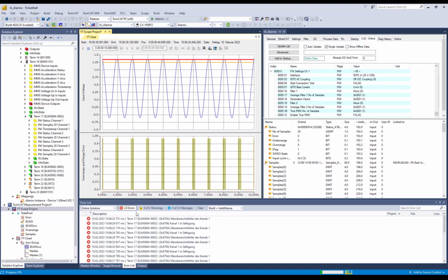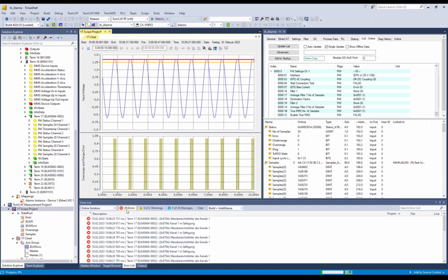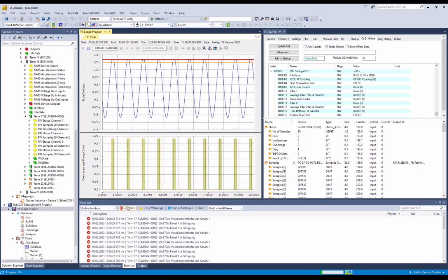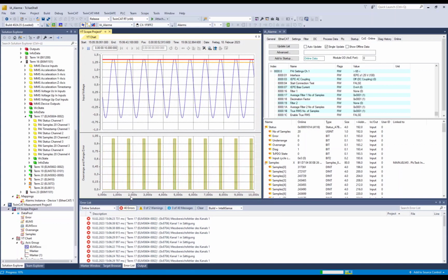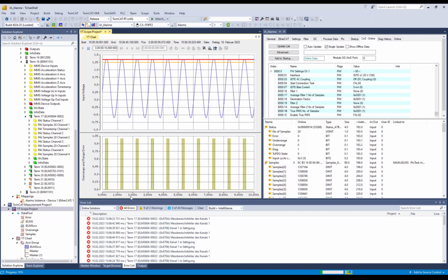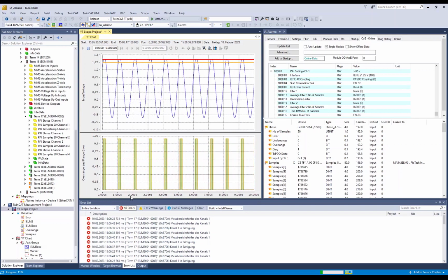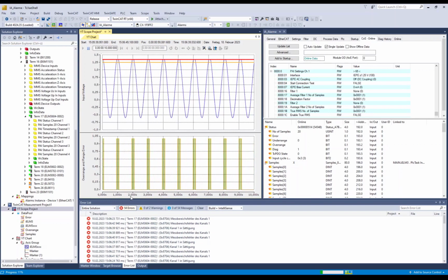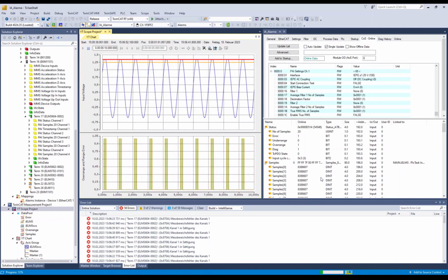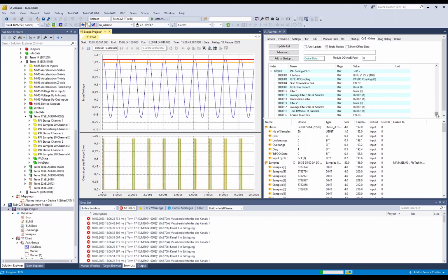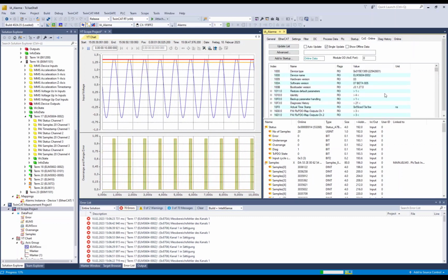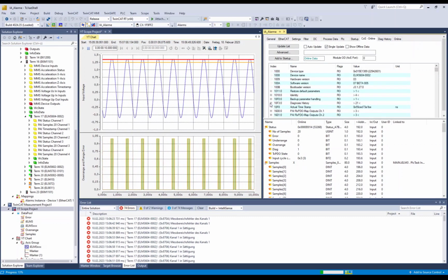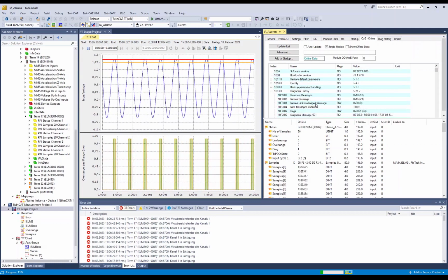And I want to get rid of these errors. You see that it's counting. So if you have lots of exceedances, for example, high vibration levels during startups, or if you have a quarter bridge sensor, a strain gauge with a problematic soldering, then you get lots of errors, and you can deactivate this on the terminal. Therefore, we go to the COE of this terminal and take a look at the diagnosis history.